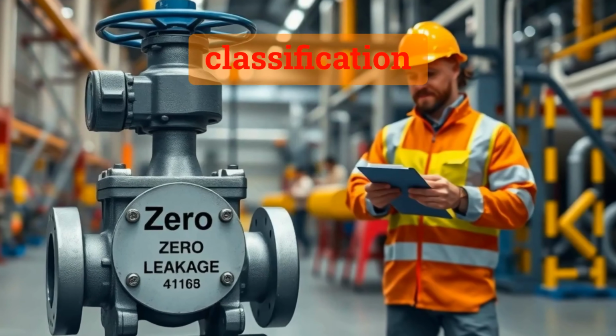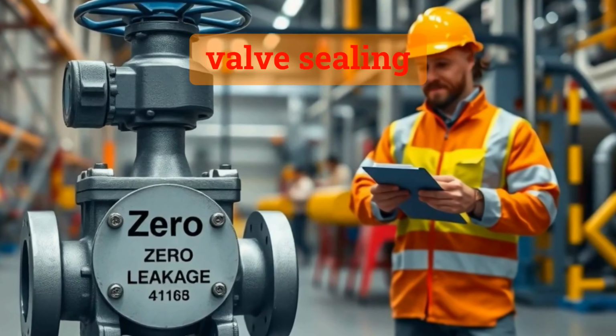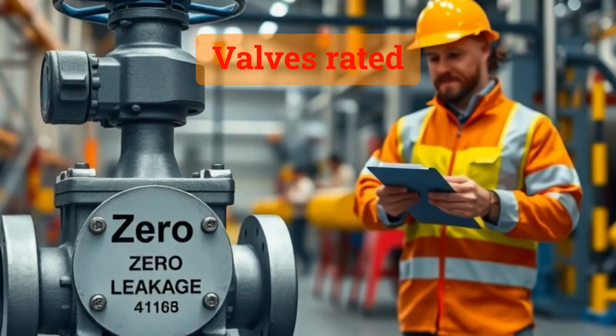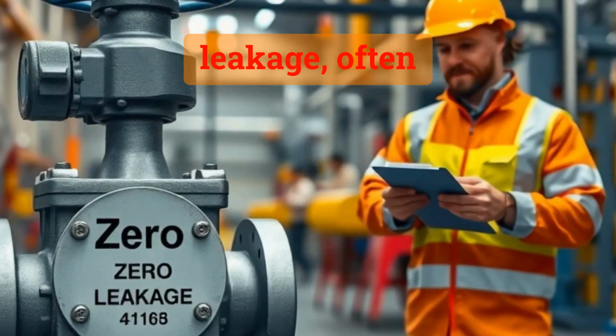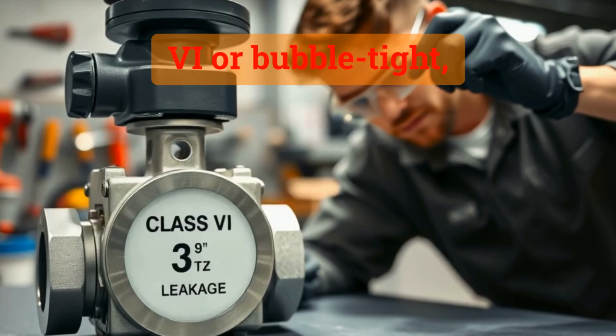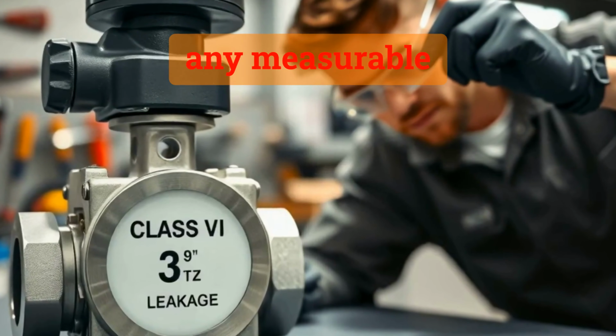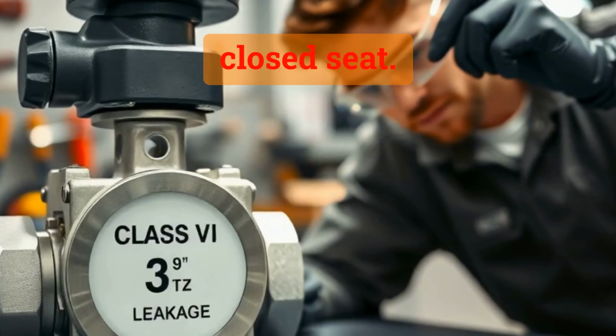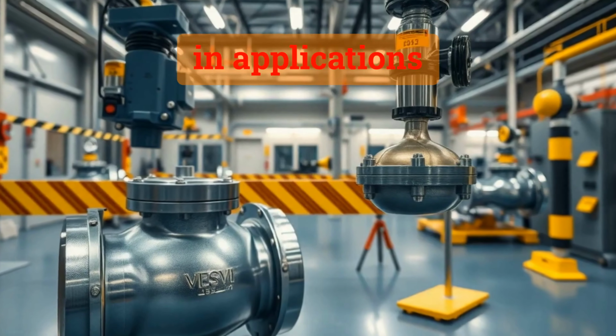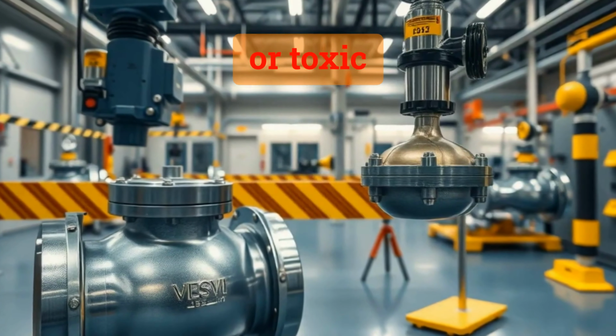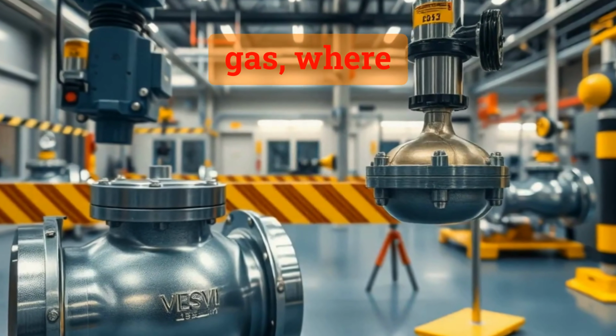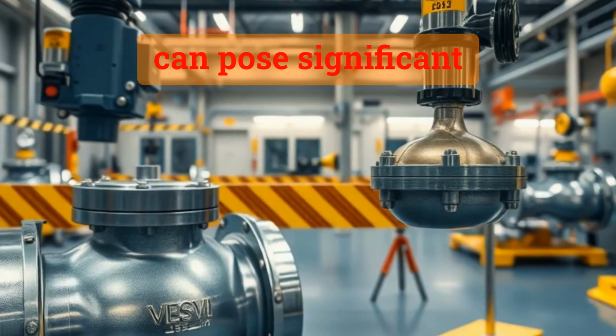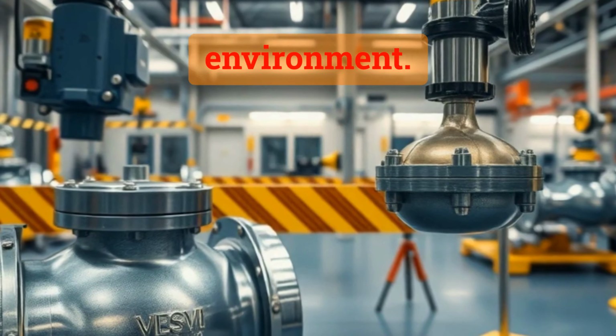Zero leakage classification stands as the gold standard for valve sealing performance. Valves rated for zero leakage, often referred to as Class 6 or bubble tight, are designed to prevent any measurable flow through the closed seat. This is particularly vital in applications involving hazardous or toxic media, such as chlorine gas, where even the smallest leak can pose significant risks to personnel and the environment.